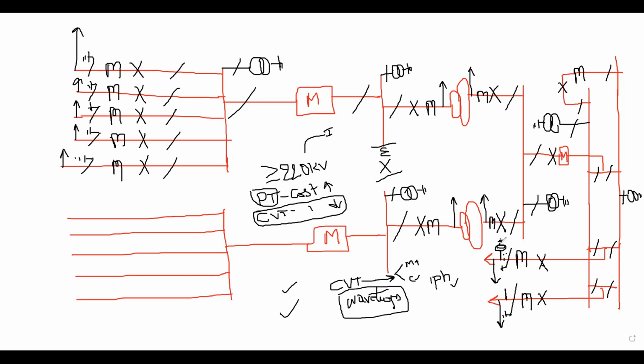For the lines you can also place a potential transformer, but at present, for cost optimization, you have the CVTs on the line ends. These are the CVTs on the board, and these are the bus potential transformers. If you see 220 kV and 400 kV, the bus PTs are also CVTs only. So this is the actual requirement of CVT for PLCC and FOT. We should have a potential transformer at the line; it could be a CVT or a PT, whatever it may be.